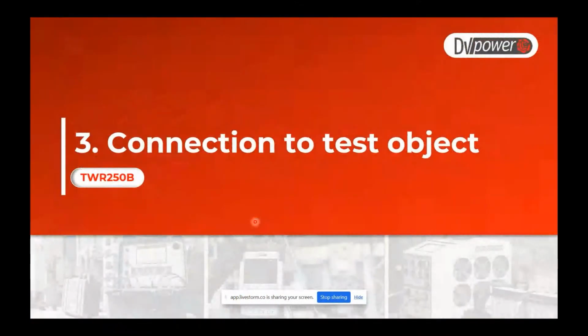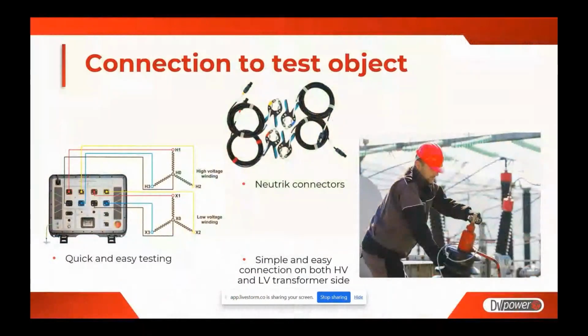Now a couple of slides about connection to the test object. Here you can see that with this device you can perform a single connection. So once you connect the TWR250B to the test object, you don't need to remove these cables. On this picture, you can see these clamps. They are really easy to connect to the terminal. So with these clamps, it's practical in the field.